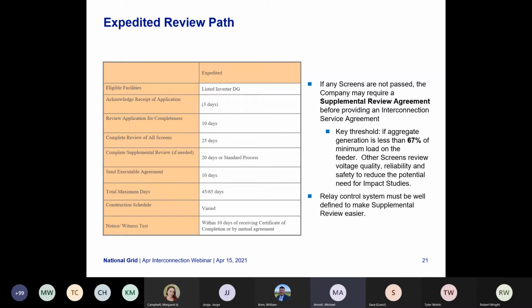The key threshold for the screens is aggregate generation less than 67% of the minimum load on the feeder. Other screens review voltage quality, reliability, and safety to reduce the potential need for impact studies. The relay control system must be well defined to make supplemental review easy. Following the screening, it may go to supplemental review if required.